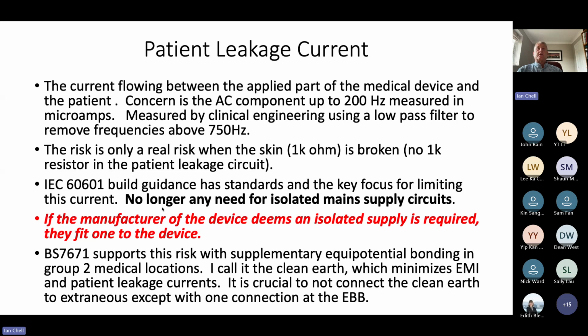Okay. So for all of this, there is the IEC 60601 build guidance standard, and it is the key focus for limiting this current. So there's no longer a need for isolated mains supply circuits. Now you're thinking, well, what about limiting in this? Well, quite simply, if a device needs an isolated supply, the device manufacturer fits it to the device. So that is where the problem of isolated supplies has shifted to. It's no longer a need to do this with the mains circuits.